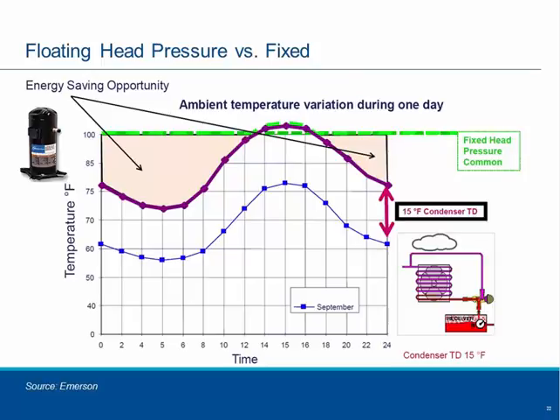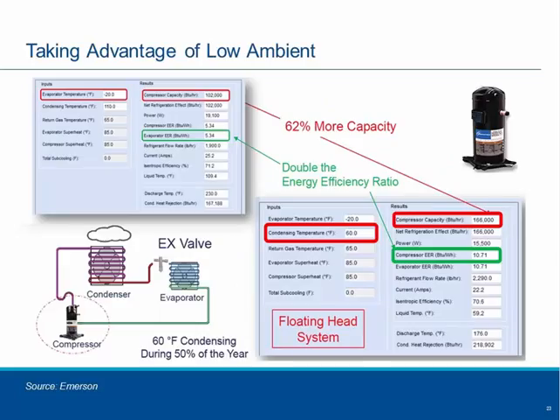The 15 degrees Fahrenheit temperature difference between ambient and the saturated condensing of the condenser is very typical, and that shaded region shows that there's energy-saving opportunities. And these energy-saving opportunities really exist in a lot of locations, not just in the northern climates, but even in Atlanta, for example, or in the desert regions where at night temperatures can get quite cool. There are a lot of energy-saving opportunities, and let me quantify that for you.